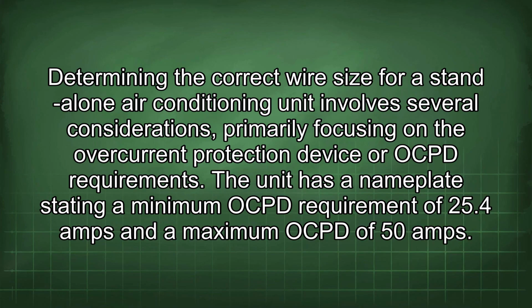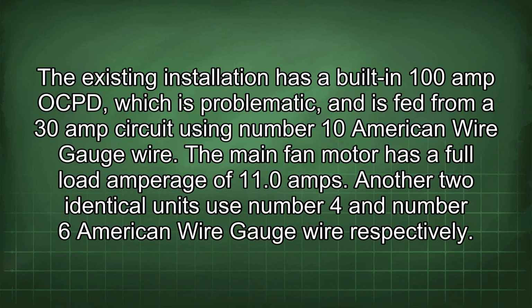Determining the correct wire size for a standalone air conditioning unit involves several considerations, primarily focusing on the overcurrent protection device, or OCPD, requirements. The unit has a nameplate stating a minimum OCPD requirement of 25.4 amps and a maximum OCPD of 50 amps. The existing installation has a built-in 100 amp OCPD, which is problematic, and is fed from a 30 amp circuit using number 10 American wire gauge wire.